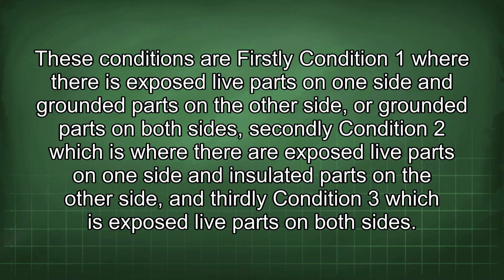These conditions are, firstly, condition 1, where there are exposed live parts on one side and grounded parts on the other side, or grounded parts on both sides. Secondly, condition 2, where there are exposed live parts on one side and insulated parts on the other side. And thirdly, condition 3, which is exposed live parts on both sides.